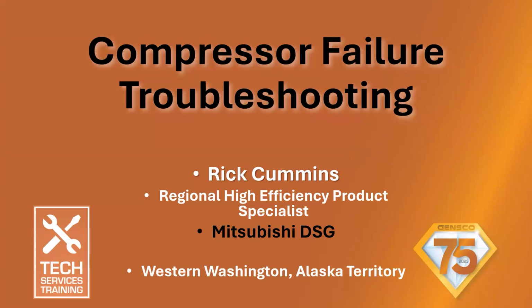Today, we're going to talk about compressor failures, how to diagnose that it has failed, reasons and causations for the failure, and some of the things you need to do at the end when you're going to replace the compressor, or even if you decided to replace the equipment, what should be checked before you move onward.